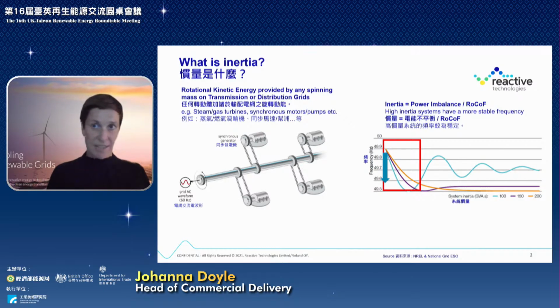On the right-hand side you can see a graph showing the output of modelling done by National Grid in the UK. They wanted to answer the question: what happens to my system frequency if there's a trip of 500 megawatts under different inertia conditions? The orange graph shows the frequency response at the highest inertia condition, and the blue line shows the frequency response at the lowest inertia condition.